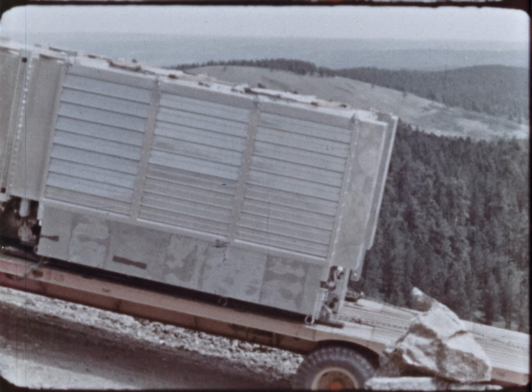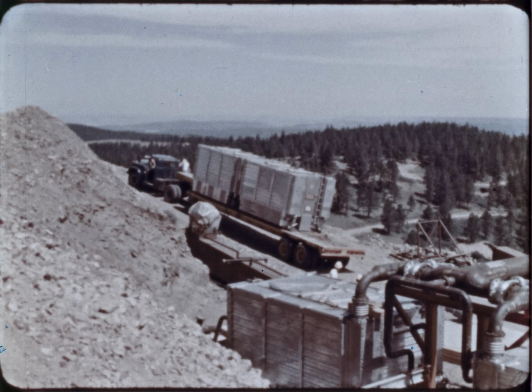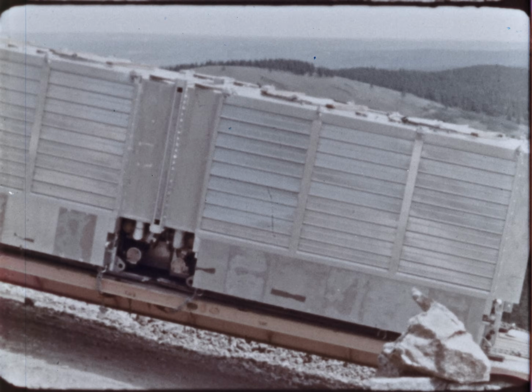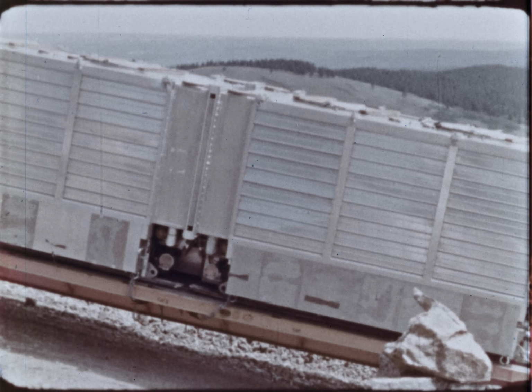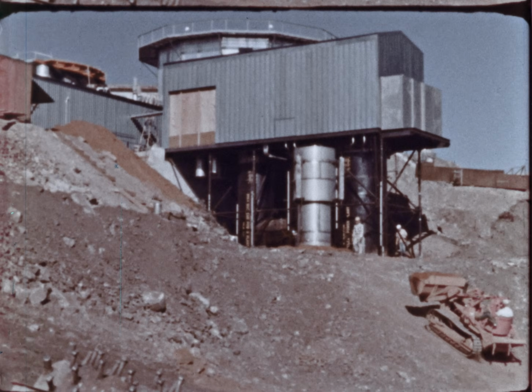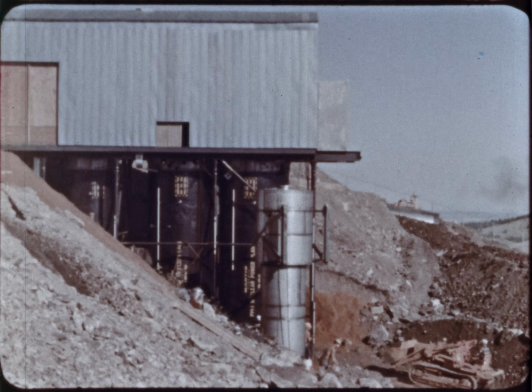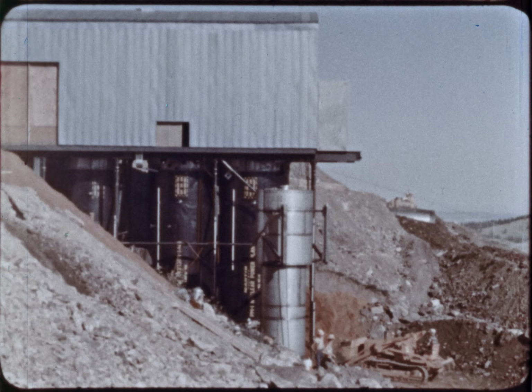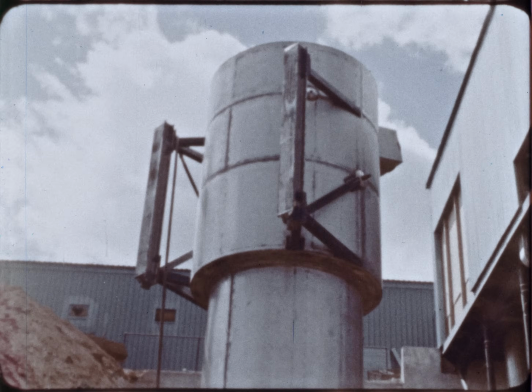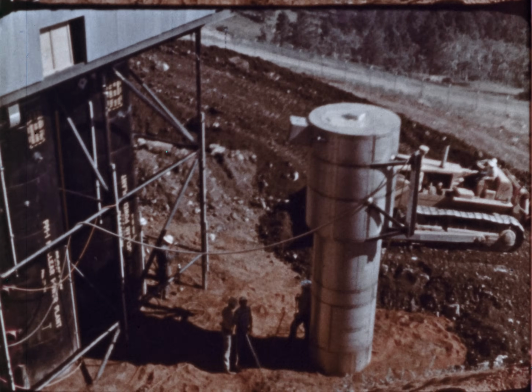The basic plant was assembled at the site from 16 packages. It could be relocated the same way. 4 packages contain miscellaneous equipment, but the heart of the PM-1 is in the remaining 12 packages, divided into the primary and secondary systems. The primary system is made up of 3 of these packages. There are 4 tanks, reactor, steam generator, and spent fuel core tanks grouped together. The radioactive waste disposal tank is a part of the 3rd package. It is shipped in the spent fuel tank.